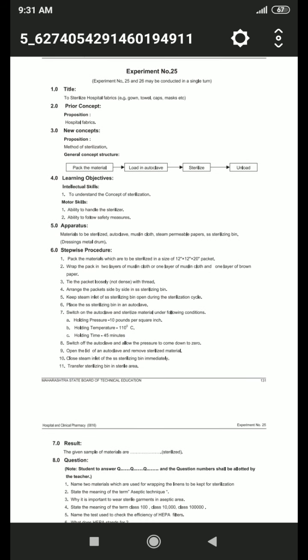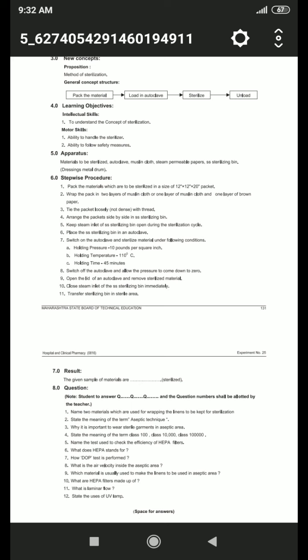Holding pressure is 10 pounds per square inch, holding temperature is 110 degrees Celsius, and holding time is 45 minutes. Then switch off the autoclave and allow the pressure to come down to 0. Then open the lid of the autoclave, remove the sterilized materials, and close the steam inlet of the SS sterilizing bin immediately. Then transfer the sterilizing bin to the sterile area. Okay, then for the result, take the sample of materials and write down your result here.